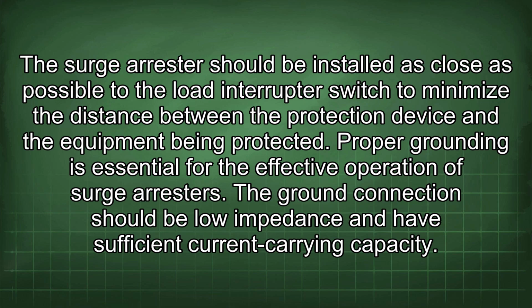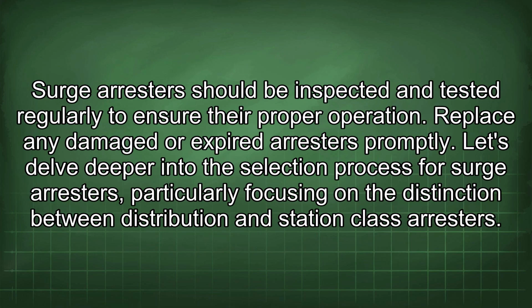Proper grounding is essential for the effective operation of surge arresters. The ground connection should be low impedance and have sufficient current carrying capacity. Surge arresters should be inspected and tested regularly to ensure their proper operation. Replace any damaged or expired arresters promptly.